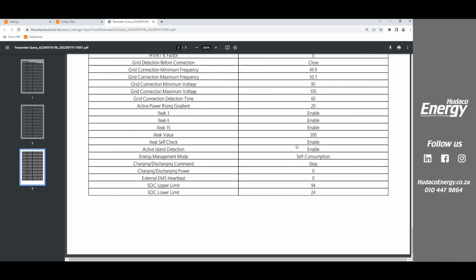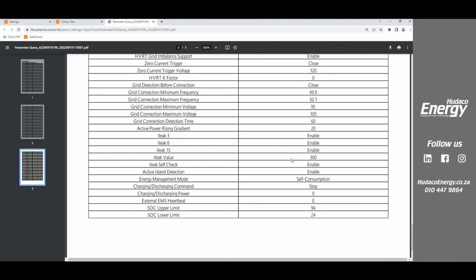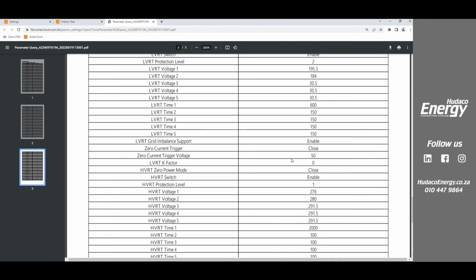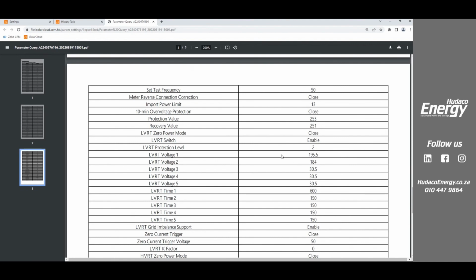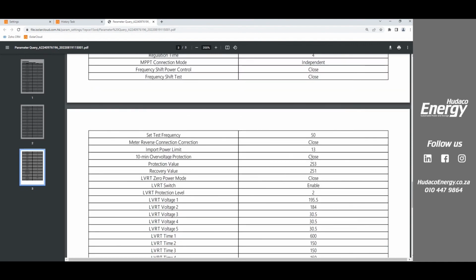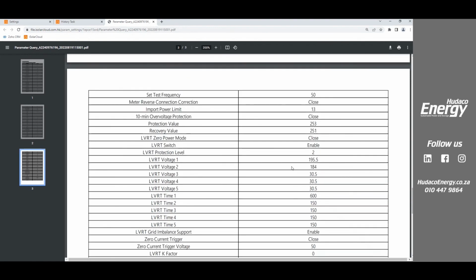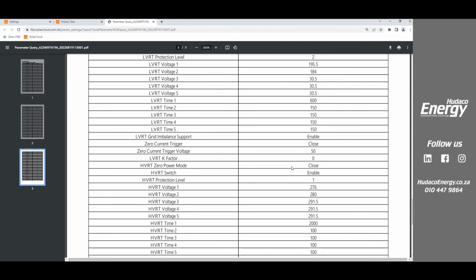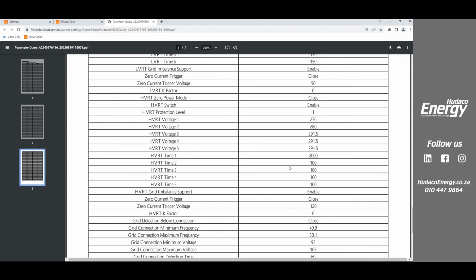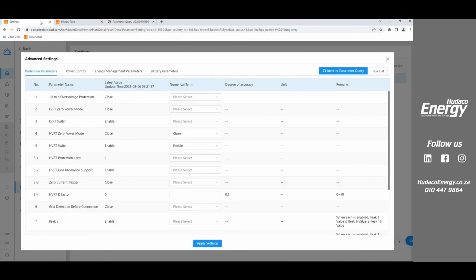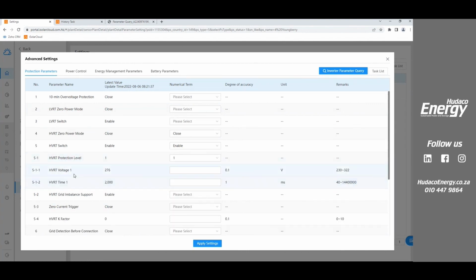You can also set where it comes back and where it reconnects. So in my particular case, see, here's your standard 253 to 251. In my case, I've set it to, I think, 254 or 253 that it reconnects. So where you would do that is you would come in here. I would select 1. When I select 1, I can put different values in there. It's currently set to 276 for 2000 milliseconds.